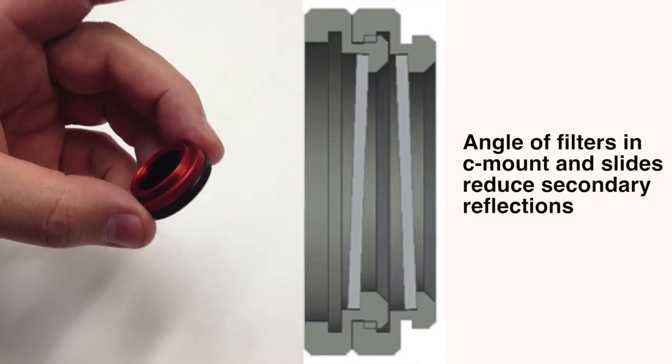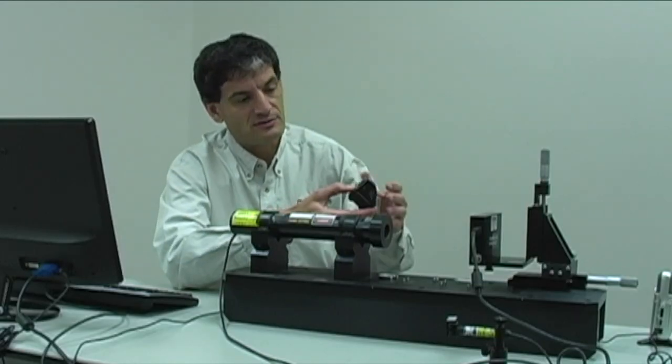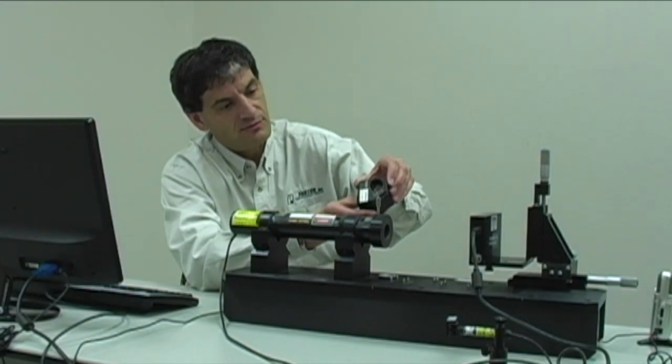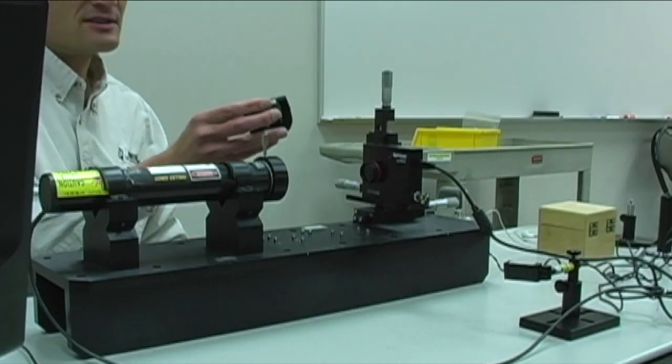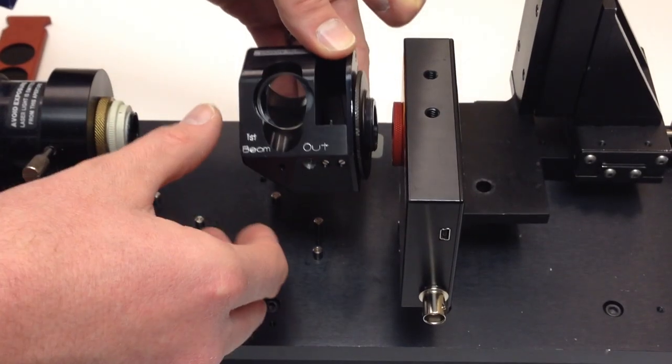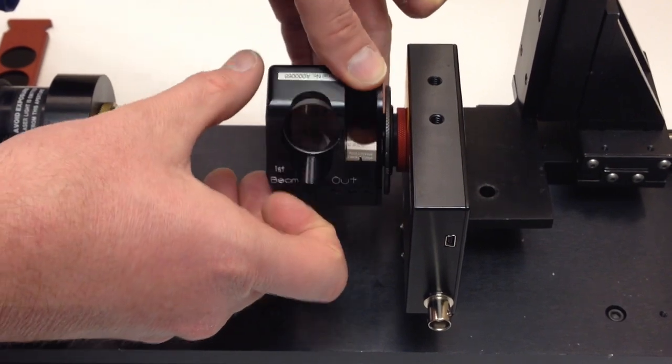So what you need to do for high power lasers is use something which has a front surface reflection. So this is the LBS 300. I'll show you how it attaches to the camera. I'm just going to screw it on here.